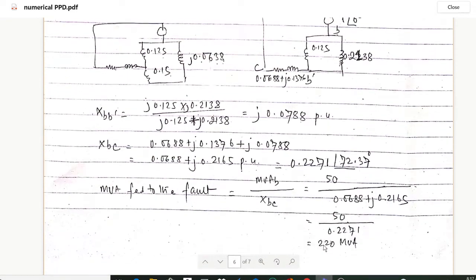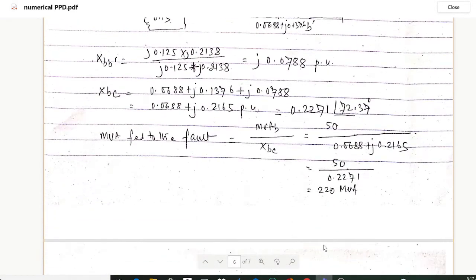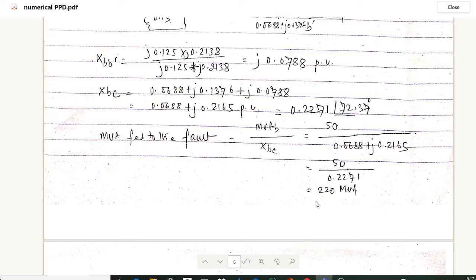The MVA fed into the fault is: MVA_fault = MVA_base / X_BC = 50 / 0.2271 = 220 MVA.